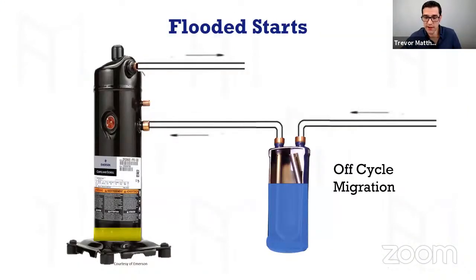Okay, let's go. So, flooded starts. What causes a flooded start? The compressor's off, nothing's running. You have an accumulator. Oh, the accumulator's protecting the system. Well, the accumulator only protects against flood back. And you need to understand this, because if you add an accumulator as a band-aid and don't see what's going on with the system, you will run into a lot of other problems. So the system's off, the accumulator has a bunch of refrigerant in it, but the compressor's colder, we'll say. If that compressor's colder, that refrigerant's going to want to migrate.